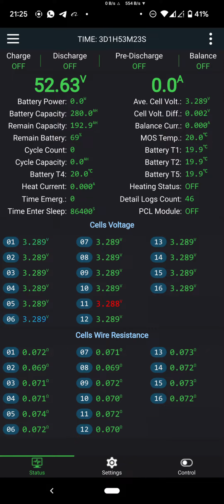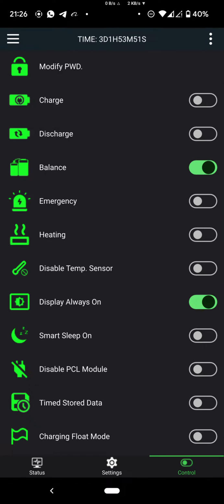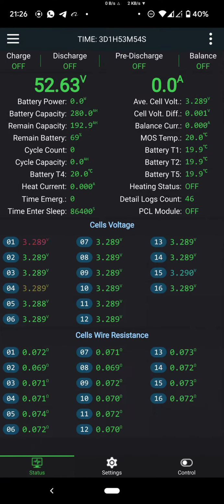Under that, we can see the charge MOSFET status, the discharge MOSFET status, pre-discharge, and the balancing status. Keep in mind this doesn't indicate or reflect the choices on the control tab. It is only an indication of what the BMS decides to enable or disable at this instant, respecting, of course, the parameters in the settings tab. As you can see here in the control tab, balancing is enabled, but here the value is off since the requirements for balancing are not met yet. This is also true for charge and discharge.